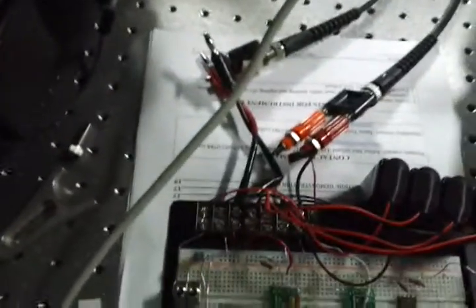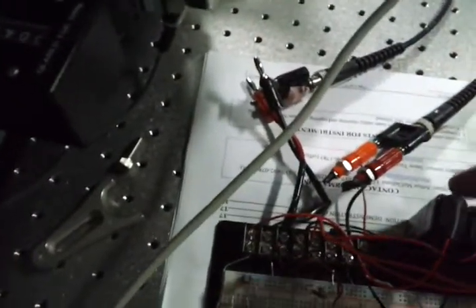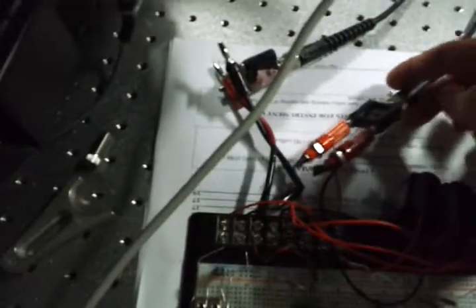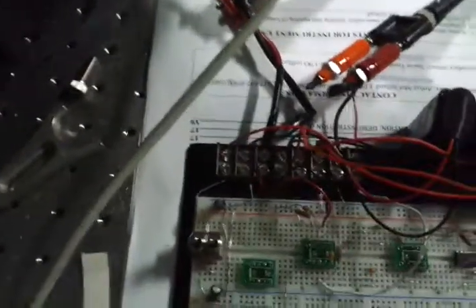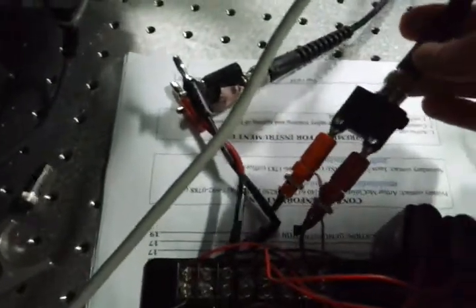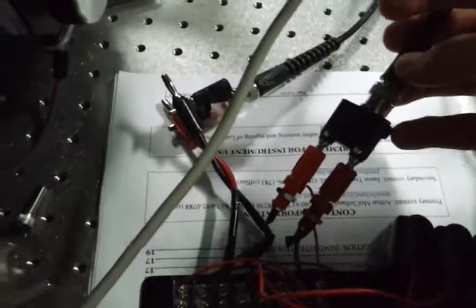The banana clips here are for the signal in, this one, the red and black combination of signal in. These orange and red are signal out. Make sure that you don't accidentally switch which one is which. Note always that in both cases the ground is the black wire. Also on these BNC adapters, this little notch on the outside here where my pinky is, that's the ground side, so make sure that's connected to ground.